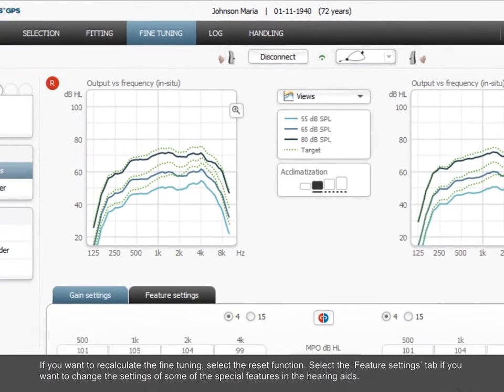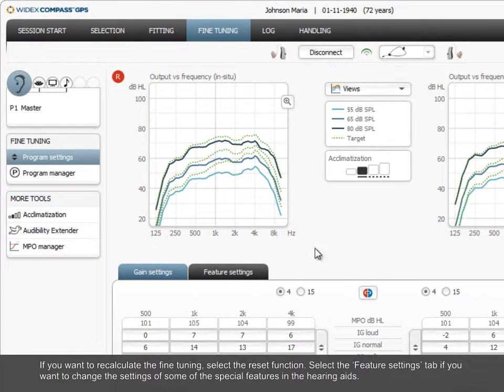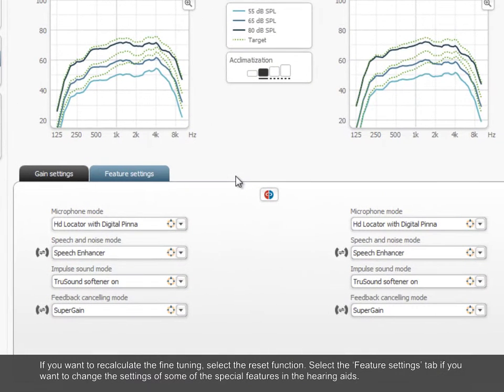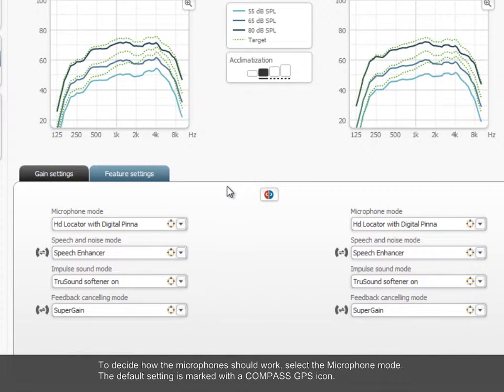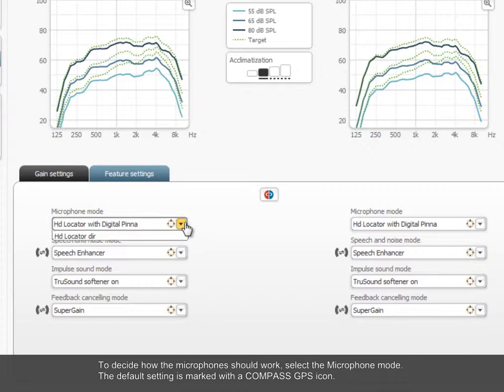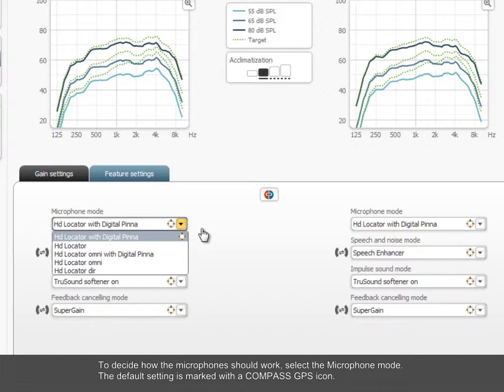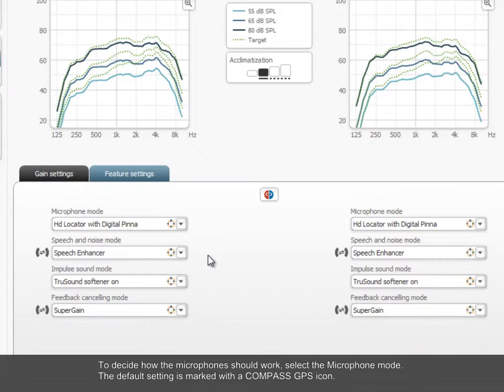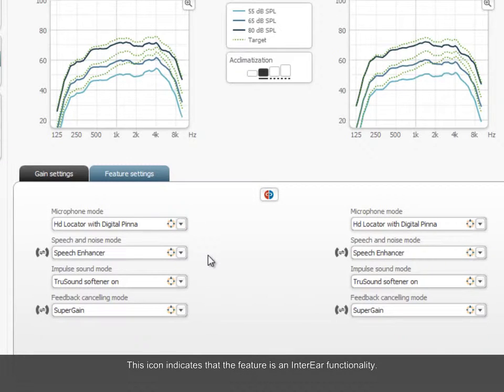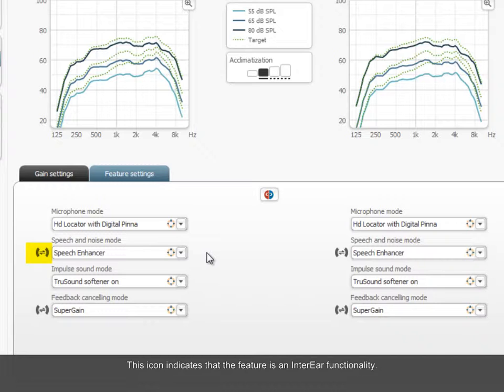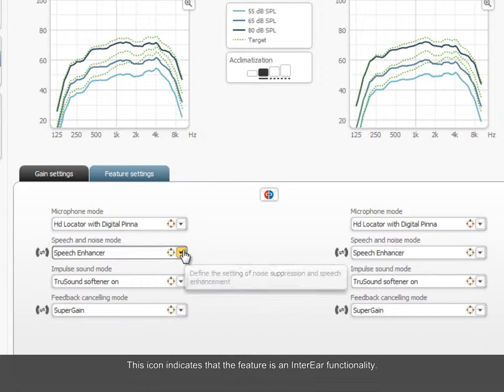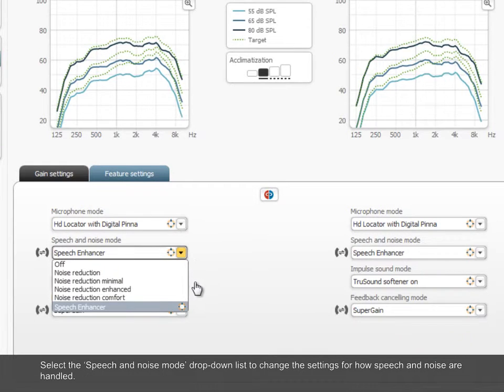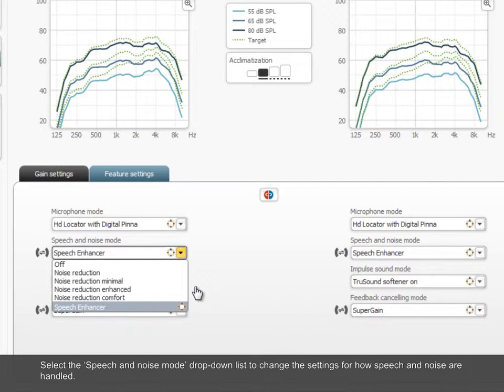Select the Feature Settings tab if you want to change the settings of some of the special features in the hearing aids. To decide how the microphones should work, select the Microphone Mode. The default setting is marked with a Compass GPS icon. This icon indicates that the feature is an inter-ear functionality. Select the Speech and Noise Mode drop-down list to change the settings for how speech and noise are handled.